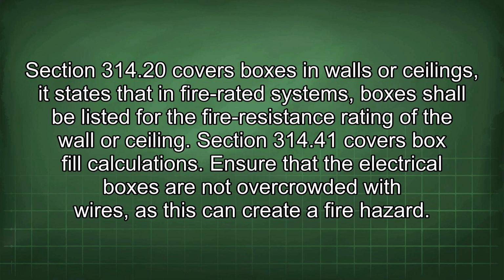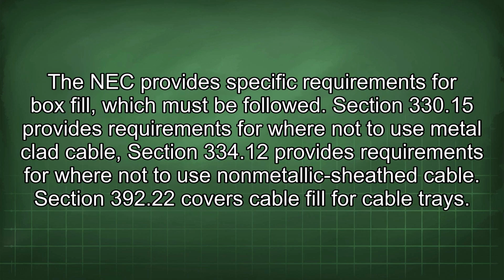Section 314.41 covers box fill calculation. Ensure that the electrical boxes are not overcrowded with wires, as this can create a fire hazard. The NEC provides specific requirements for box fill, which must be followed. Section 330.15 provides requirements for when not to use metal-clad cable. Section 334.12 provides requirements for when not to use non-metallic sheath cable.